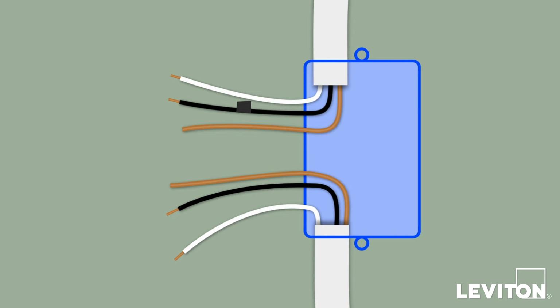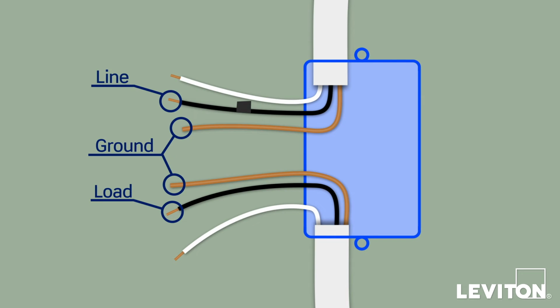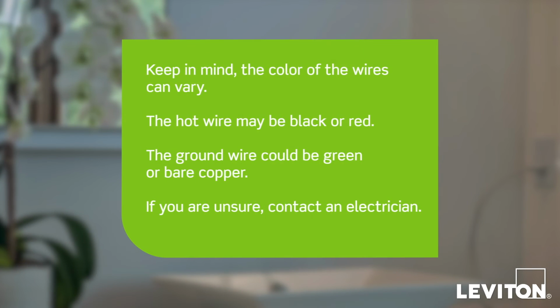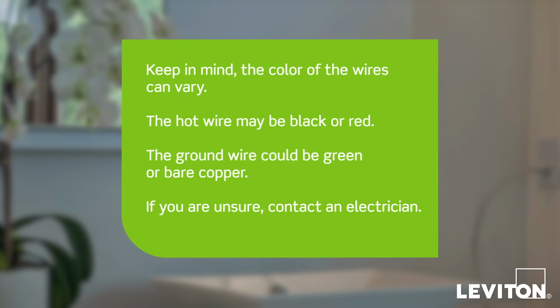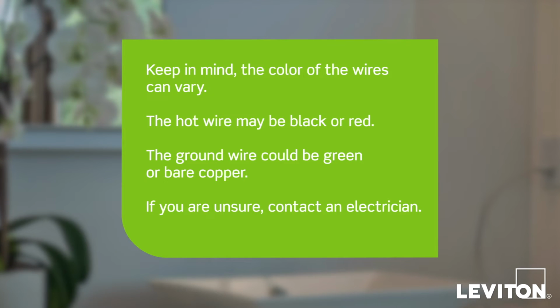In this example, in the wall box there's a black wire, which is the line or hot wire, another black wire, which is the load wire, two bare copper wires, which are the ground wires, and two white wires, which are the neutral wires. Please keep in mind that the color of the wires can vary. The hot wire may be black or red, and the ground wire could be green or bare copper. If you're unsure, contact an electrician.